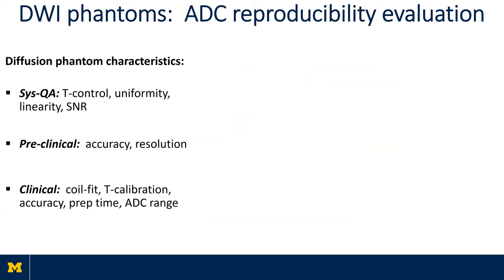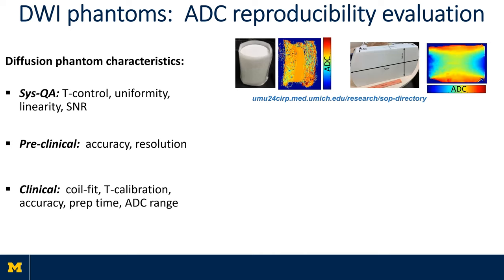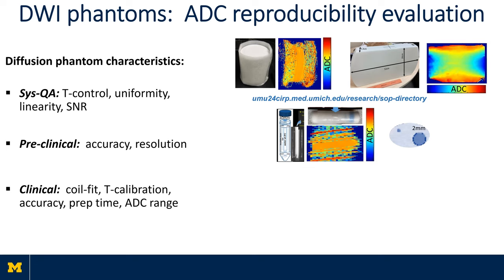Several physical ADC phantoms have been implemented and used to date for system QA, preclinical, and clinical studies. For system quality assurance in a research environment, ice water provides a viable option for temperature control, good SNR, and accurate ground truth value in the tissue-relevant range of 1.1 micron squared per millisecond, but it is limited usually to one-dimensional sampling because it is usually placed in a tube. Gel-based phantoms that prevent bulk fluid motion provide large real estate and allow testing uniformity with respect to ISO center, but have lower SNR due to T2 damping and absolute diffusivity dependent on scanner room temperature.